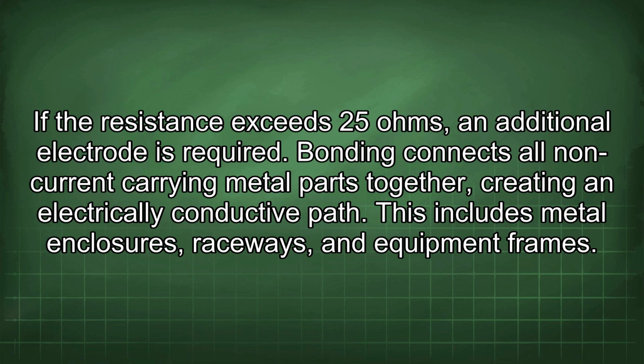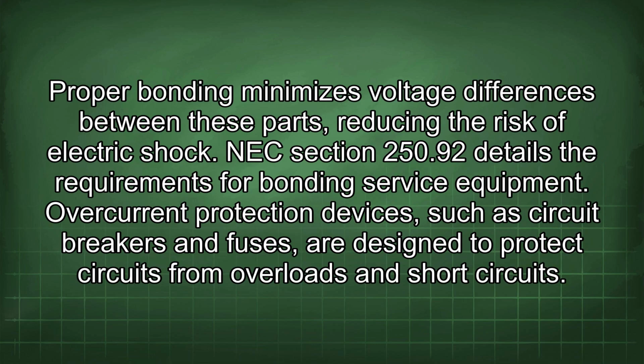Bonding connects all non-current carrying metal parts together, creating an electrically conductive path. This includes metal enclosures, raceways, and equipment frames. Proper bonding minimizes voltage differences between these parts, reducing the risk of electric shock. NEC section 250.92 details the requirements for bonding service equipment.